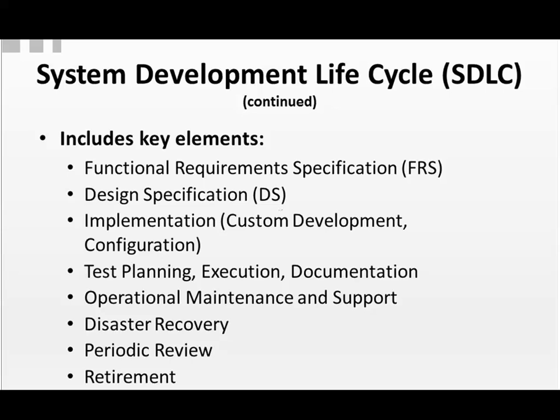But note you also need to have periodic review of every GXP system. So at least annually, or if you make a significant change to the system, you must look at all of the aspects of the system from the time it was first validated until the current time to demonstrate that it has remained in a validated state. So change control logs, any kind of changes that were made, was the system revalidated?